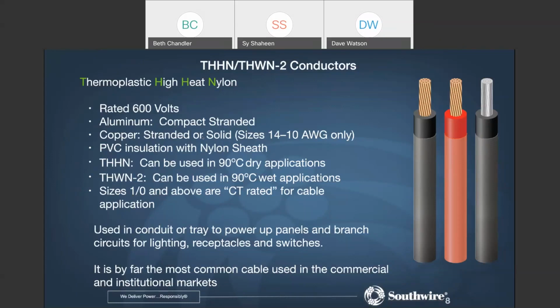University. So the aluminum products that are used for these type of conductors are going to be compact stranded. So they're going to take up less space. They have a smaller OD. There'll be less space in between each individual strand. That's necessary for the aluminum conductors because the aluminum conductivity is less compared to copper. Therefore, you have to use a larger size aluminum conductor to be able to conduct the same amount of current without exceeding the maximum temperature capability of the insulation. Therefore, in order to try to mitigate that size difference, the aluminum product is made with compact stranding. So it's a little different from the copper there.